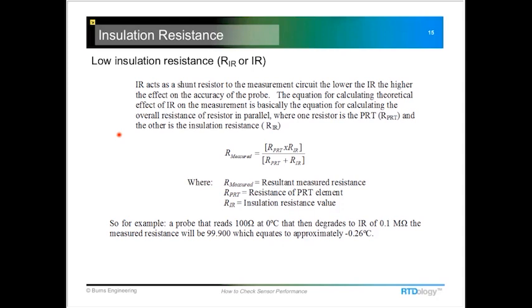So I guess we have one question here. I see, can we use a DMM for insulation resistance? And I guess the answer is yes, you can, as long as it has the capability of measuring at a high enough level to ensure that the part is good. The ones that I see frequently are not going to go up past 100 megohms. They're more in the 10 meg range. But if you do have one that has the capability for doing multiple tasks, you certainly can use that.